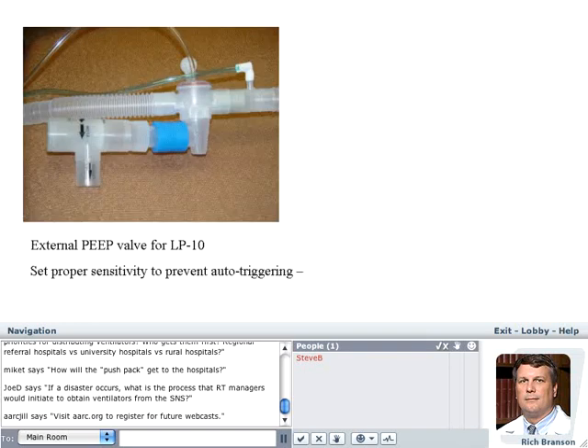This is a picture just showing you the use of a vital signs PEEP valve on the expiratory valve of the circuit, and you see both circuits for the LP10 and the impact are the same. The old style mushroom, although it's just a disc exhalation valve, and the green tubing there for monitoring airway pressure. So once you set that PEEP valve in line, you do have to reset the sensitivity in order for the patient to trigger it effectively.